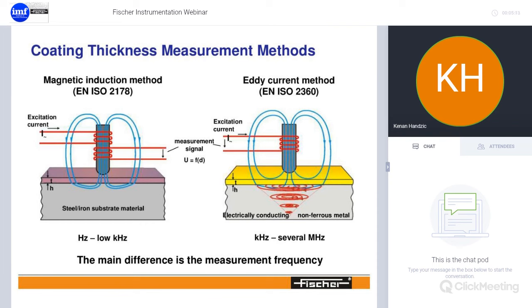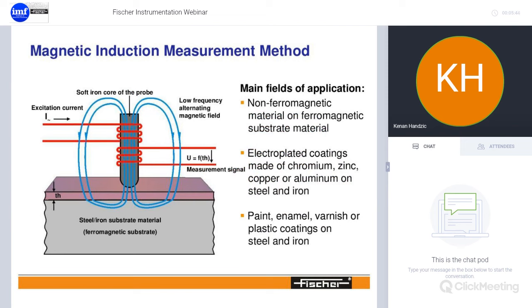Similarly, with the eddy current method, a magnetic or electrical field is generated, which generates eddy currents within the substrate or within the coating. Based on the displacement of that field, we can calculate the thickness of the material. The two main differences between these methods is the frequency range: magnetic induction operates in the hertz to low kilohertz range, whereas the eddy current method requires kilohertz to several megahertz range. This higher frequency is required to generate eddy currents within the material. For the magnetic induction probe, there is an excitation current and a measurement signal via two coils, and the displacement of the magnetic field is translated to a coating thickness.